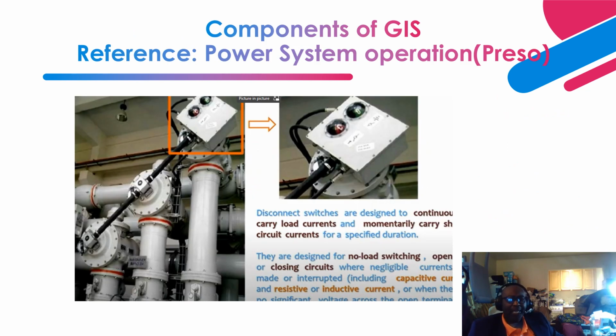Okay, next slide. I indicated that we have a disconnect switch. As you can see over here, we have the horizontal bus system for the GIS in a three-phase arrangement. To operate the disconnect switch, the GIS gives you the capability to visually see the status, whether the disconnect switch is in an open position or closed position. This is basically a visual port that gives you the ability to see the status of the disconnect switches. This is part of the safety aspect, and it delves into the benefits of the GIS, in that personnel do not come into contact with the live components inside the enclosure.